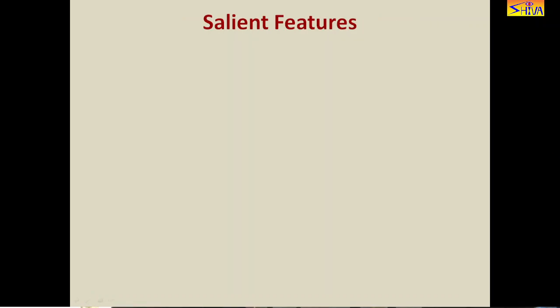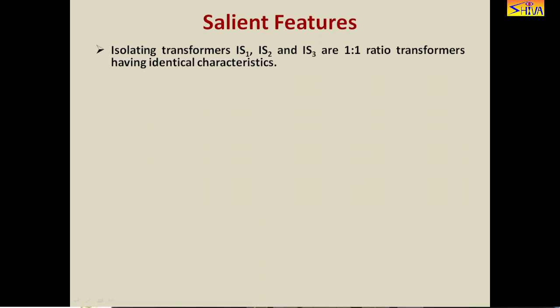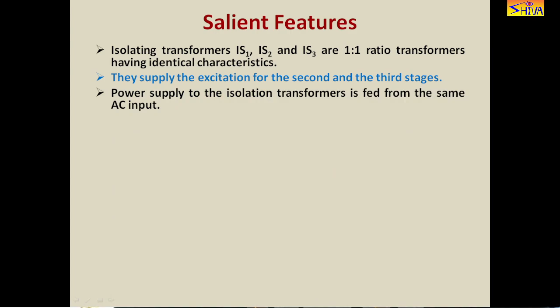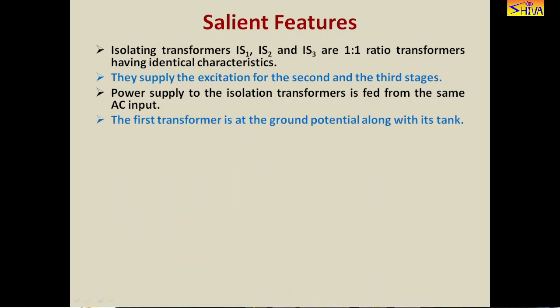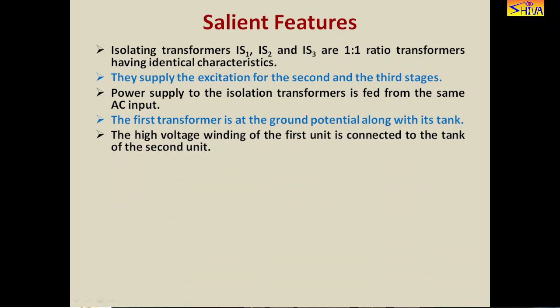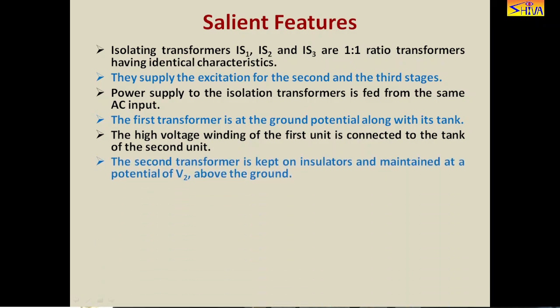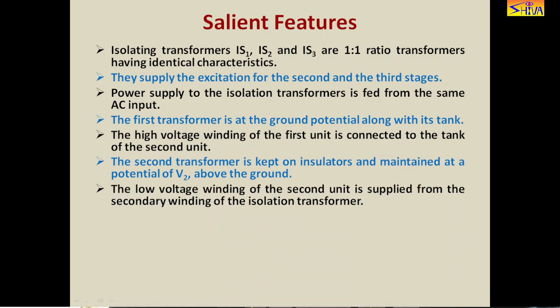The salient features of this arrangement are: IS1, IS2 and IS3 are isolation transformers having a transformation ratio of 1:1 with identical characteristics. They supply the excitation for the second and third stages. Power supply to the isolation transformers is fed from the same AC input. The first transformer is at ground potential along with its tank. The high voltage winding of the first unit is connected to the tank of the second unit, which is kept on insulators at a potential of V2 above ground. The low voltage winding of the second unit is supplied from the secondary winding of the isolation transformer.